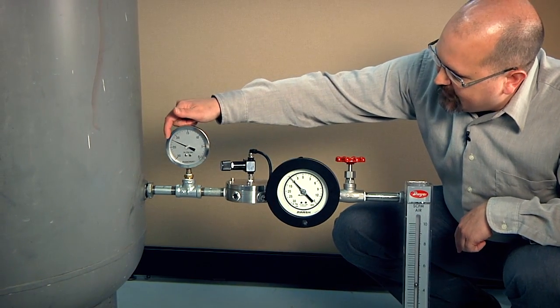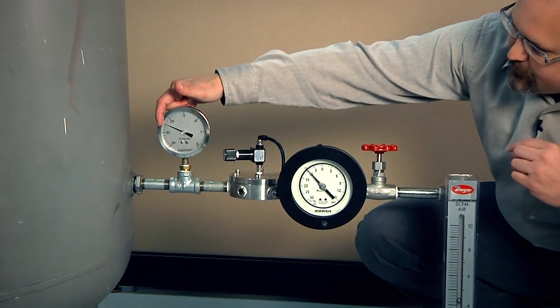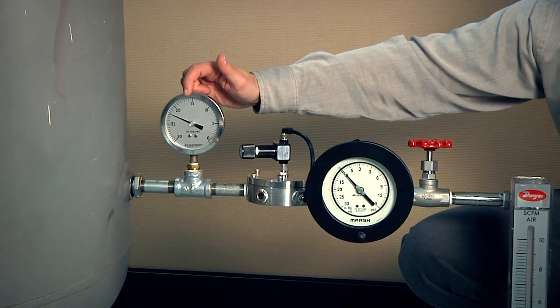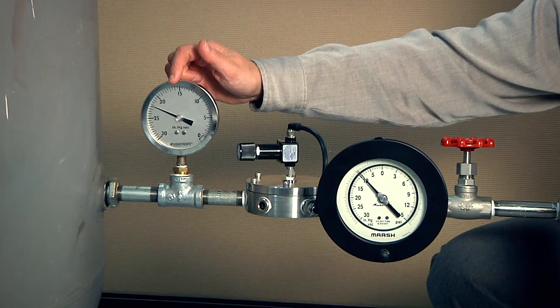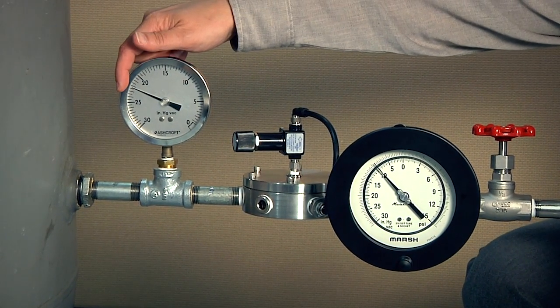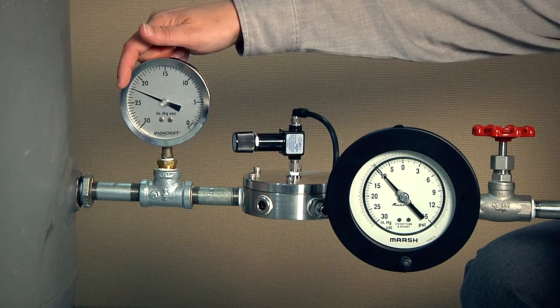We're going to take this system vacuum and we're going to drop it from about 22 and a half inches all the way down to about 15 inches of mercury. And as this happens, what I want you to notice is that...